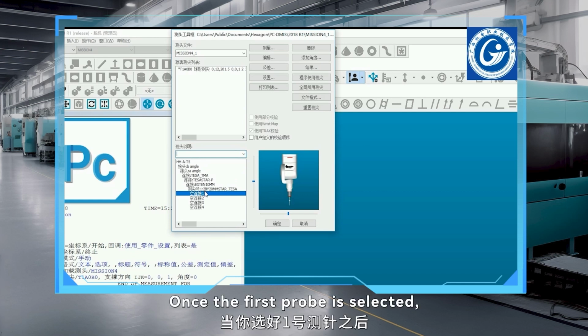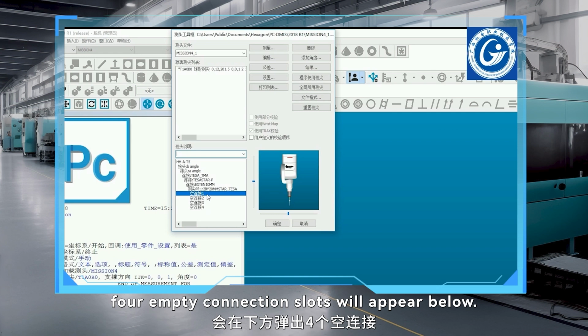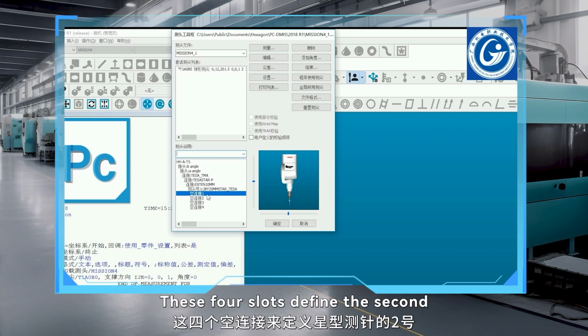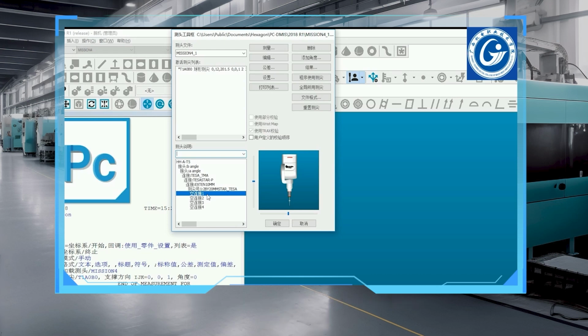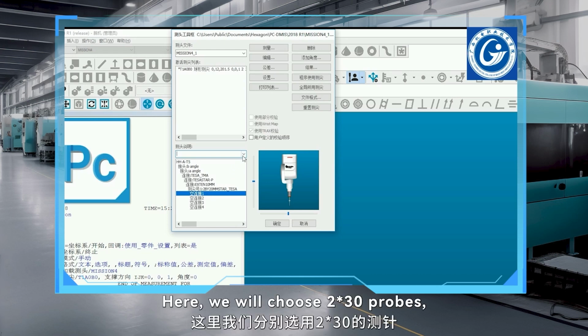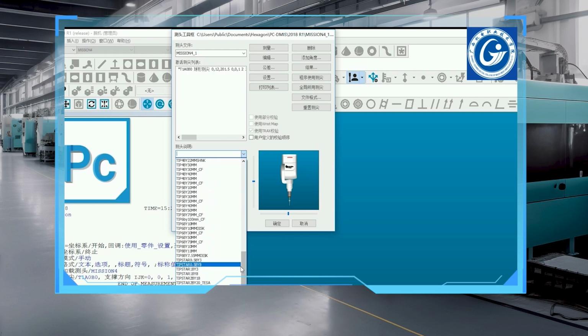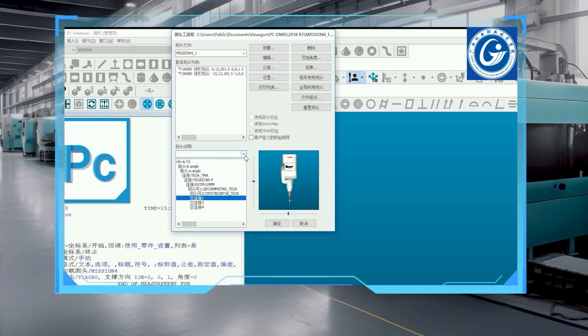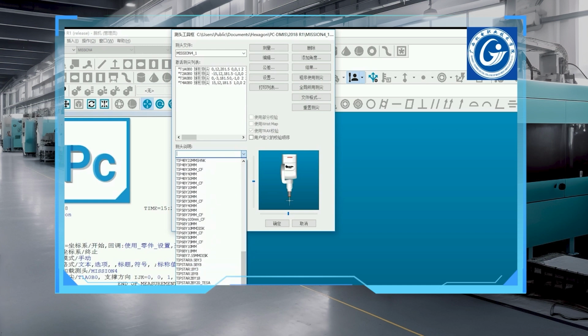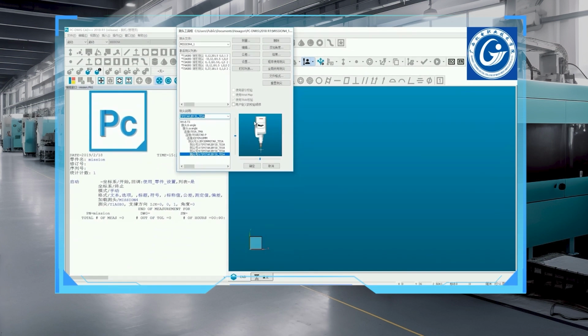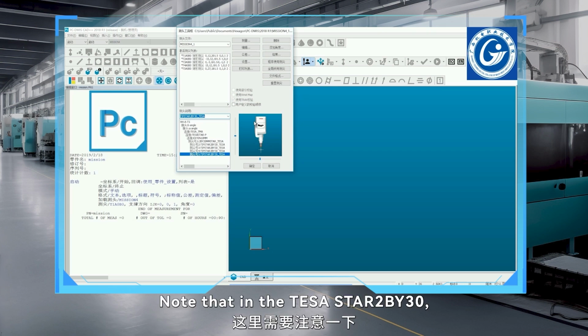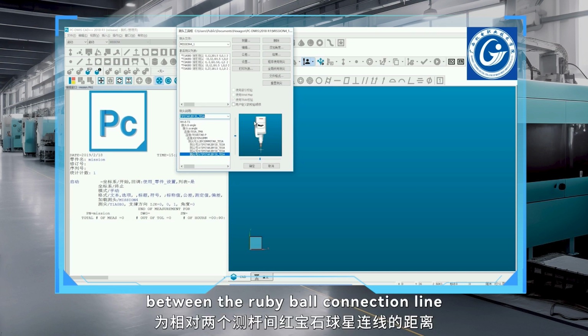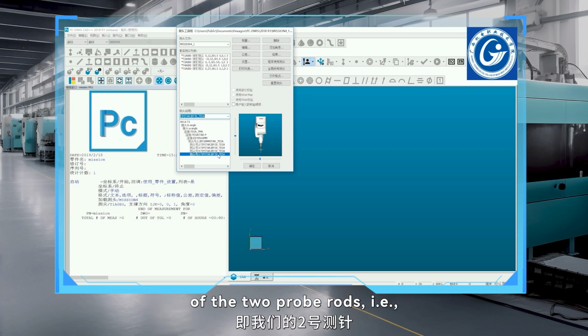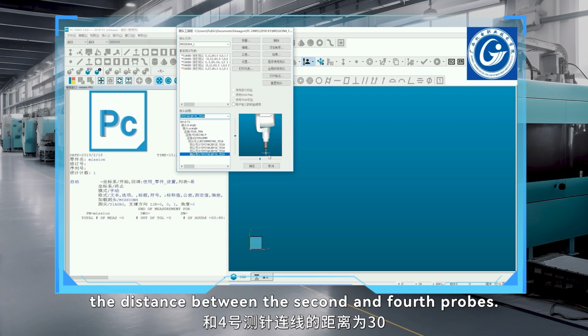Once the first probe is selected, 4 empty connection slots will appear below. These 4 slots define the 2nd to 5th probes of the star probe. Here, we will choose 2x30 probes, with the suffix TISA. Note that in the TISA star 2BY30, the 30 refers to the distance between the ruby ball connection line of the 2 probe rods, i.e., the distance between the 2nd and 4th probes.